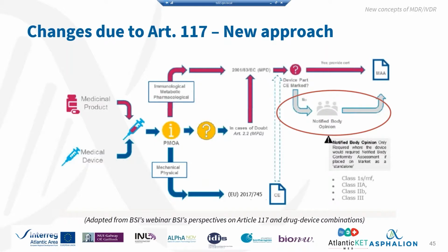Okay, what the regulation is saying is that you can have a device that is not CE marked, but it has to be assessed by a notified body nevertheless. So you have to send data on your device to a notified body, who will assess whether your device complies or not with the requirements of the regulation. Once this notified body assesses if it complies or not, the marketing authorization will be granted or not.